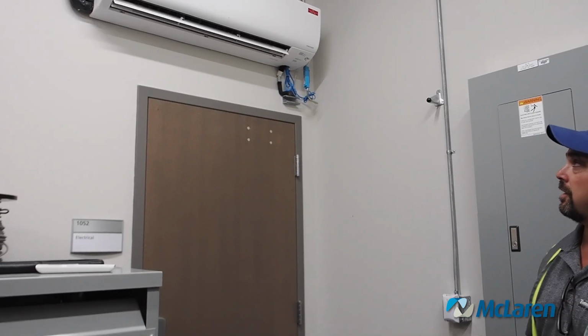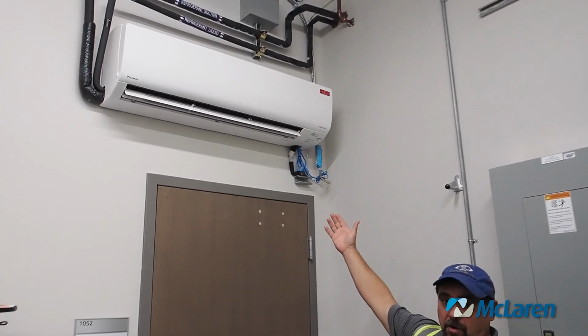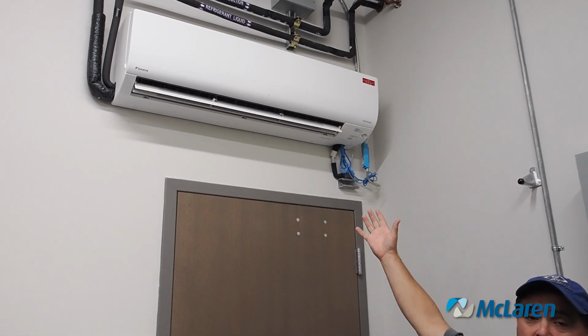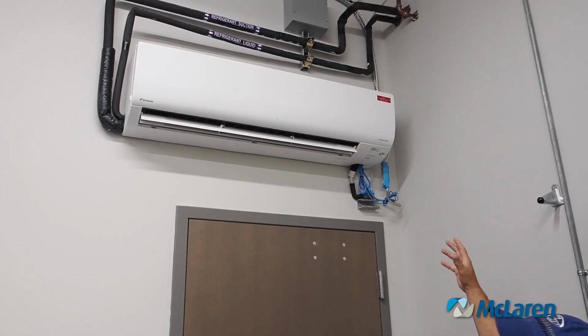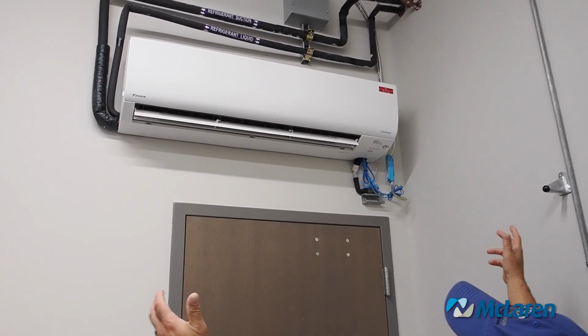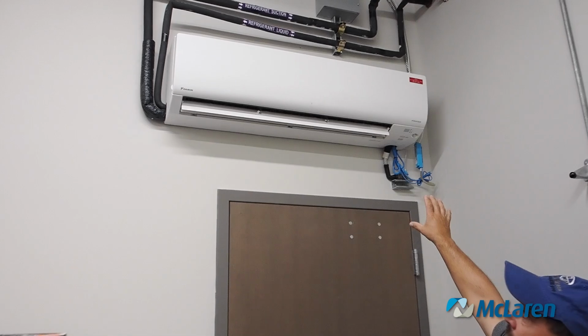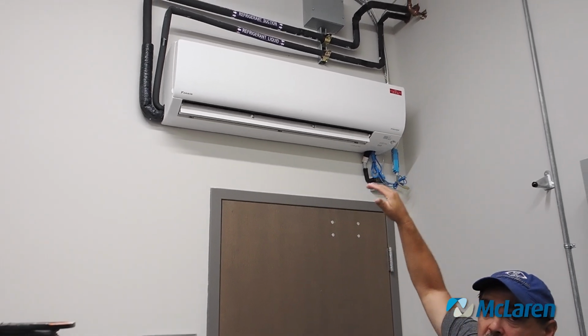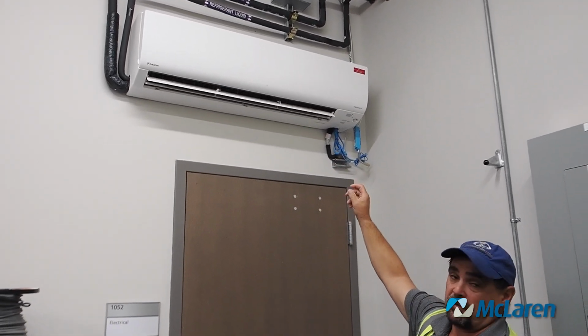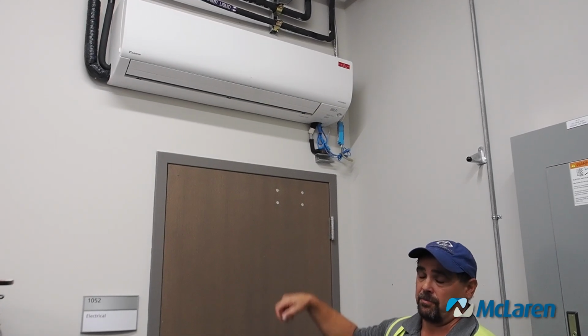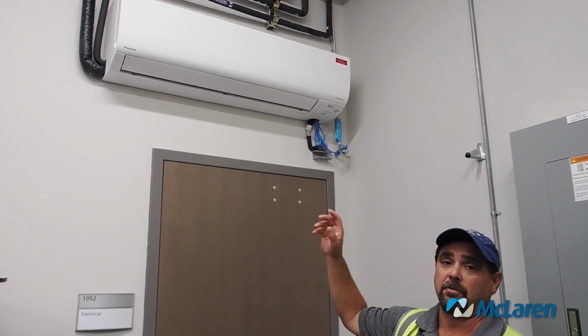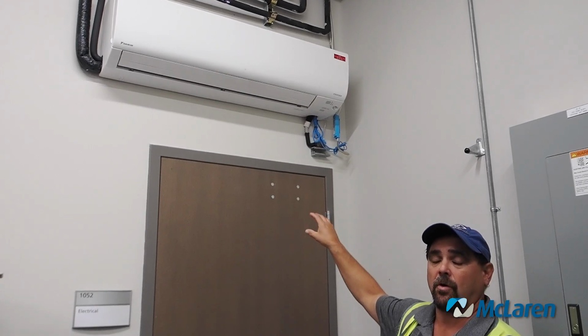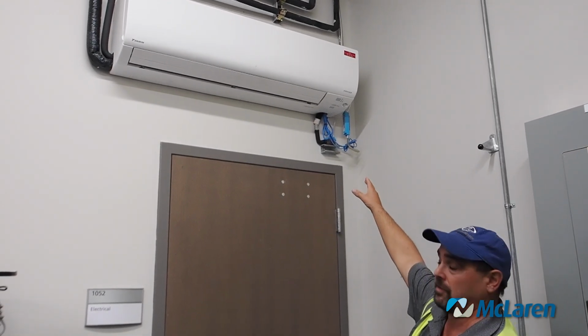The next item I would like to talk about is the actual fan coil itself. This unit requires very little maintenance. To access the filter, there's tabs on each side of the front cover plate. The front cover plate lifts up to about a 90-degree position, and there's screen filters in there that you pull out and wash gently, and then you put them back in. When you wash out the filters, please take some water and just pour gently over the evaporator coil and clean out any lint stuff that's in the condensate.